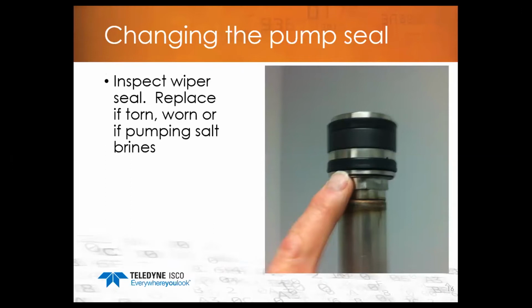Now, the wear ring typically does not have to be replaced. My recommendation would be that if you have the cylinder off and you're replacing the piston seal, it's probably a good idea to just go ahead and replace the wiper seal while you're at it. It's not necessary, because the wiper seal isn't doing any sealing, so if you only have the one seal, that's fine. But generally, when we have them here in-house for repair, we'll typically replace both seals. So when you order the seal, they don't come as a kit. You have to order the quantity that you want. So if you're going to replace both the piston and the wiper seal on the pump, you would need to order a quantity of 2.